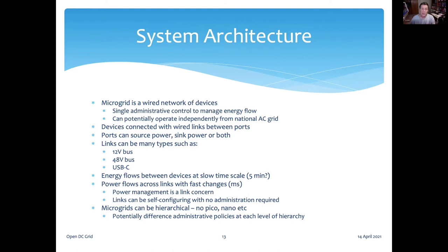Like IEEE 2030.10, we're defining our 48-volt link to be electrically compatible with the ISO 21780 standard for 48-volt electricity in mild hybrid cars, so we can use those 48-volt subsystems on our ODG microgrid. We also want to incorporate existing DC technology wherever practical. In particular, we anticipate incorporating USB-C with relatively simple bridges as additional ports on a solar home system compatible with ODG. We anticipate using USB vendor extensions to carry ODG functionality such as demand response, in a compatible way so that non-conforming USB devices can be used with reduced functionality.